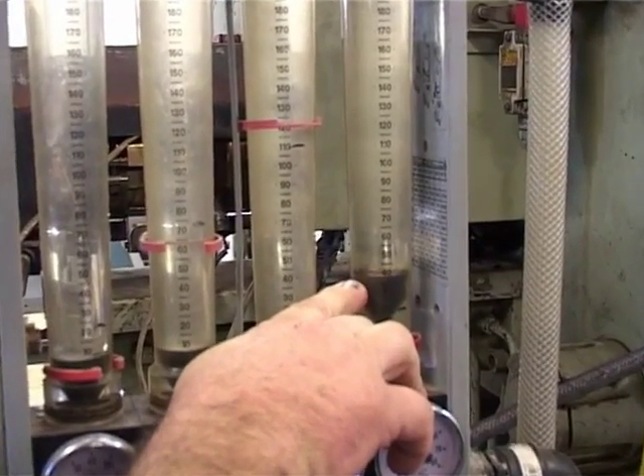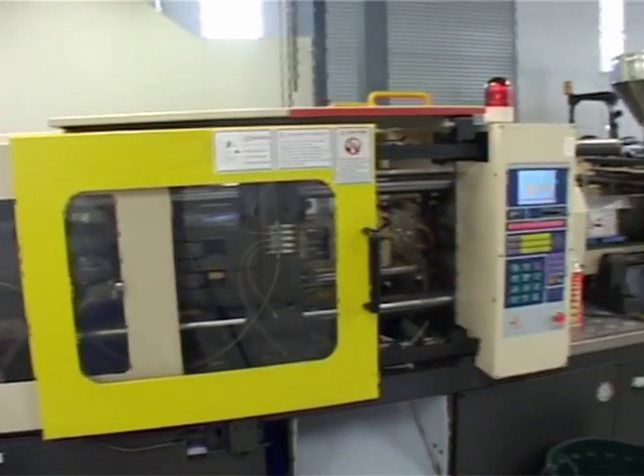Machines are nice and clean inside. We've found our pipes are no longer clogging up or having corrosion bits and pieces in them, and our tower is completely clean. The water's drinkable. The biggest benefit we've got is we have no bacterial problems and we are using no chemicals.